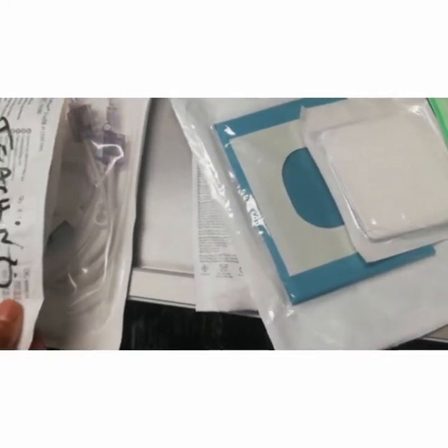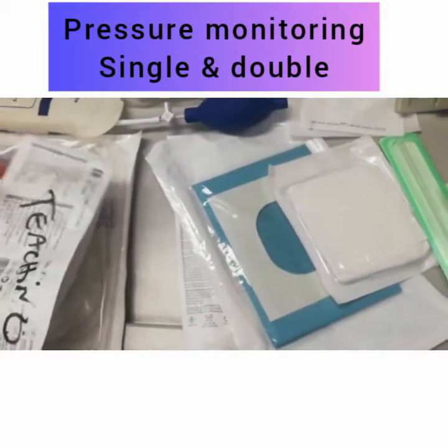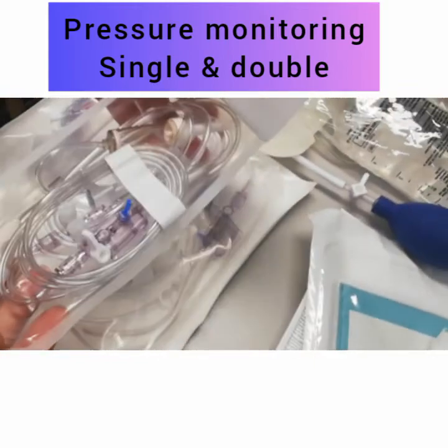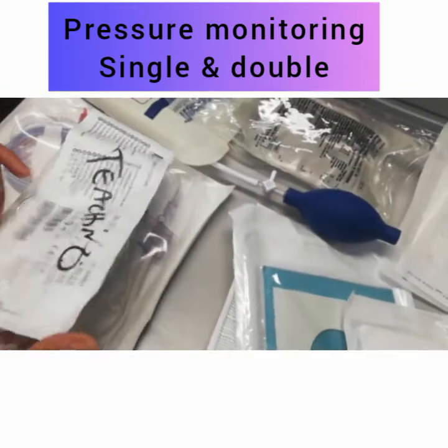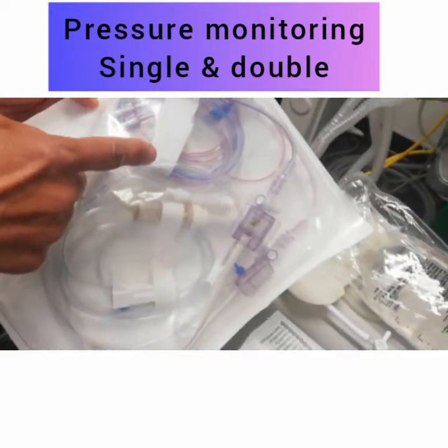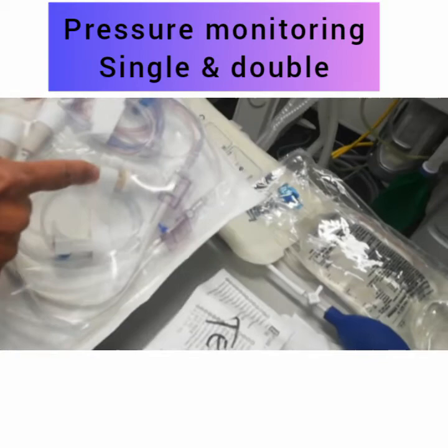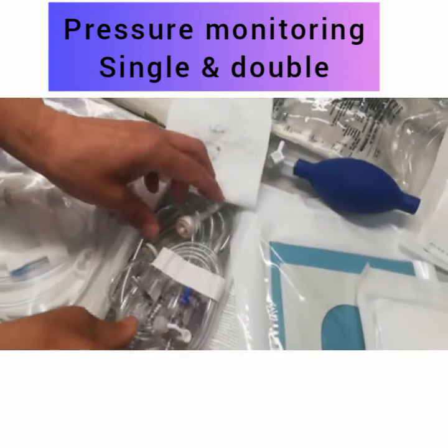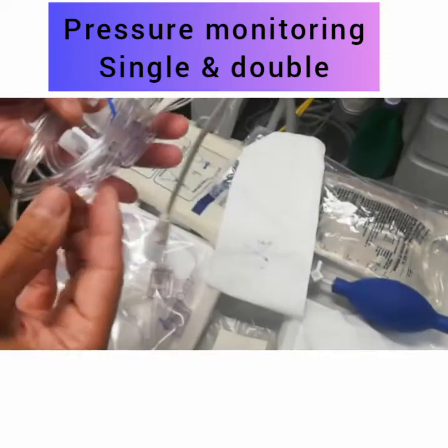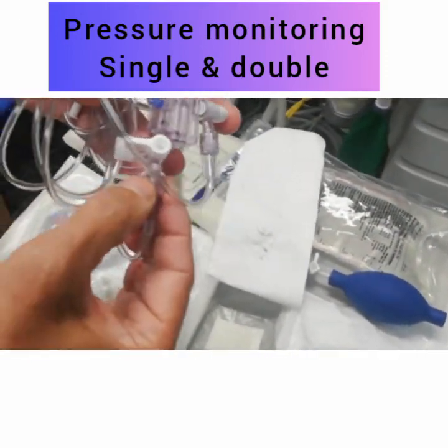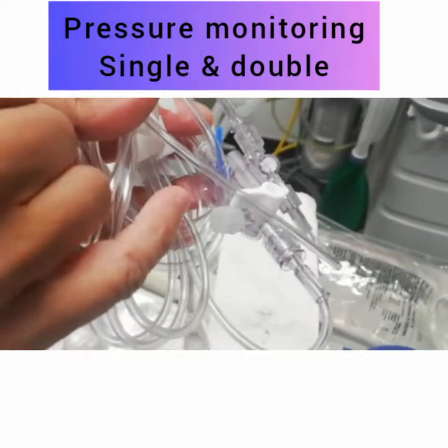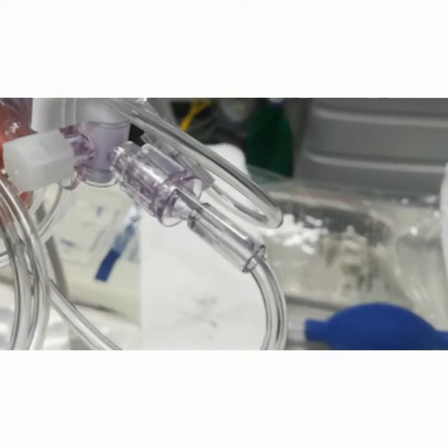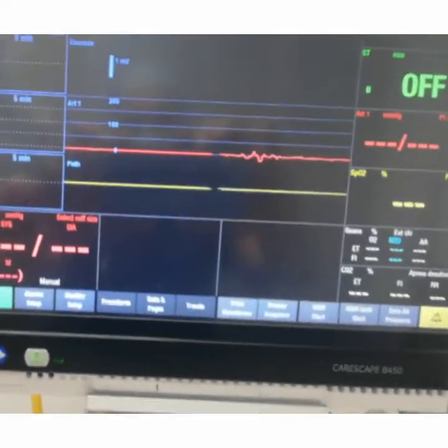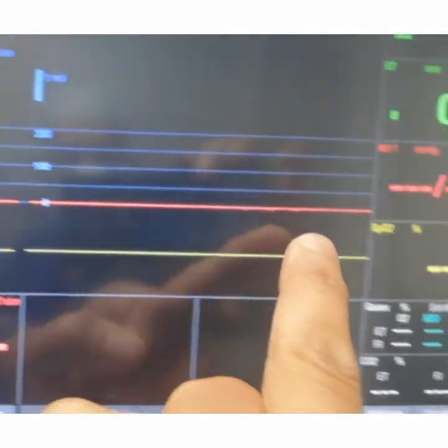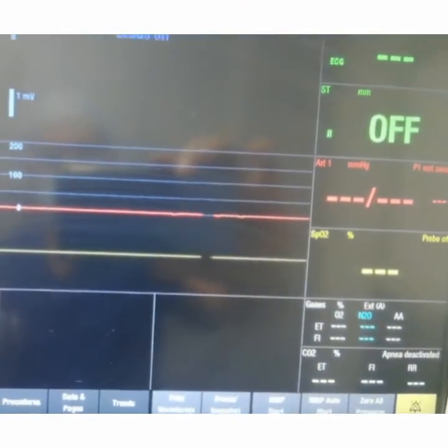Then you need a pressure monitor set. It can be a single, if you do only one line like an arterial line or CVP line, or it can be a double using the two of them, CVP line and arterial line. All those lines usually come loose, so make sure you tighten them, and all the caps come with a little hole to get rid of air bubbles. Once everything is connected, you can see a straight red line on the monitor, and if it's blue, all you can do is just swap the transducer lead.